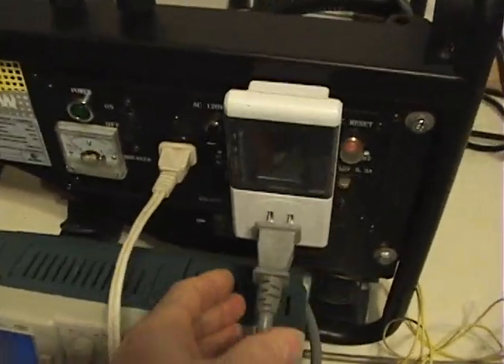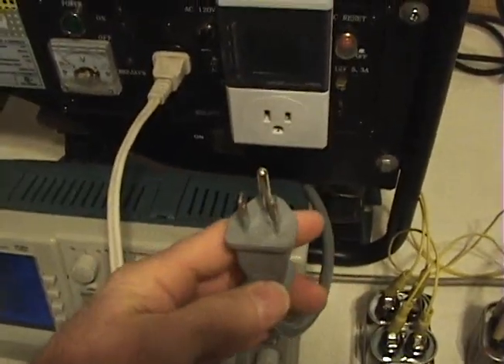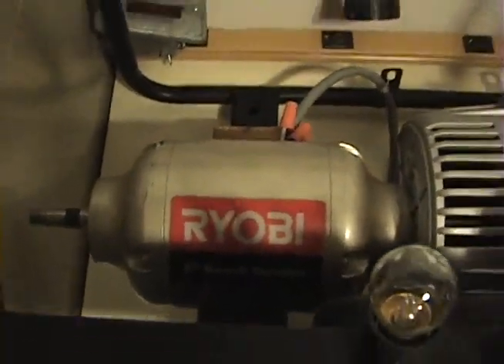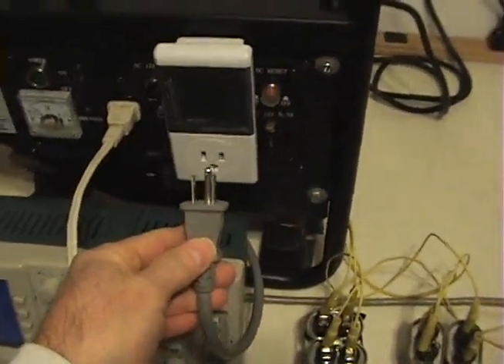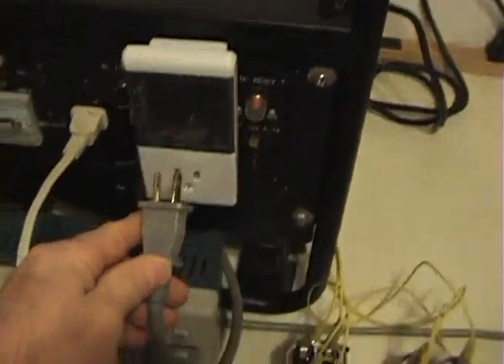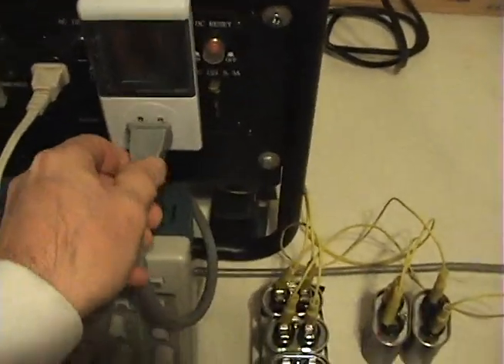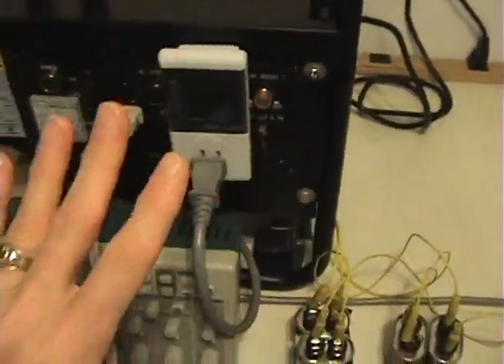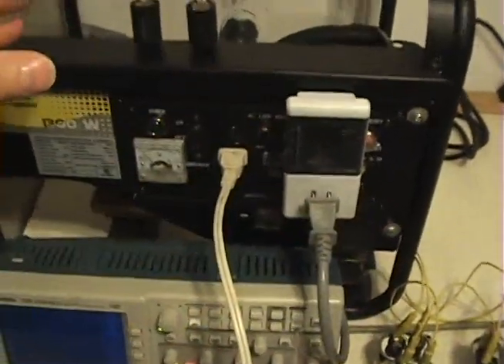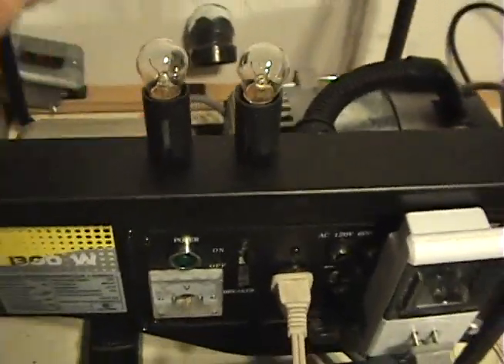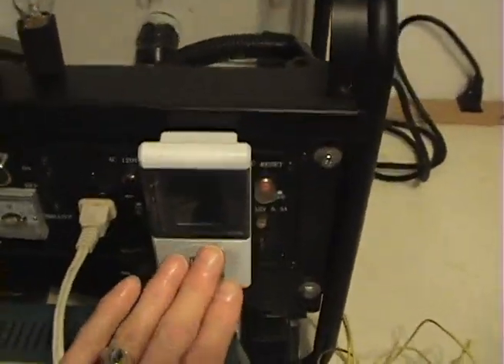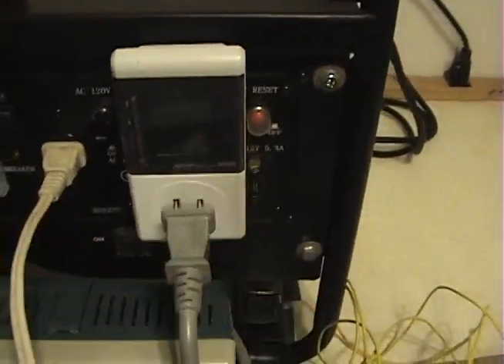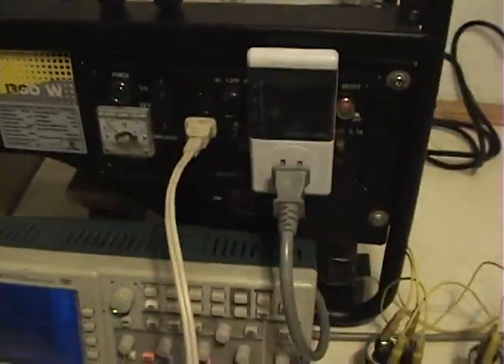In the previous video we were testing the prime mover, the induction motor, to see how much power it uses while turning the alternator head. We determined that hooking up the reactive circuit and putting it under load has zero effect as far as asking for more energy consumption from the power feeding that alternator. So I've left the setup identical here, and we've concluded there is no effect back to the prime mover of this generator.